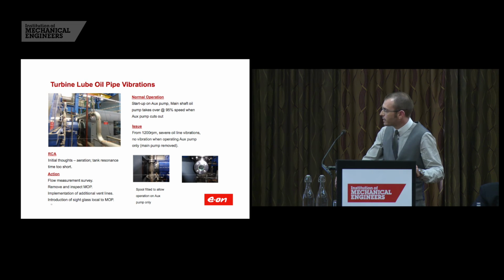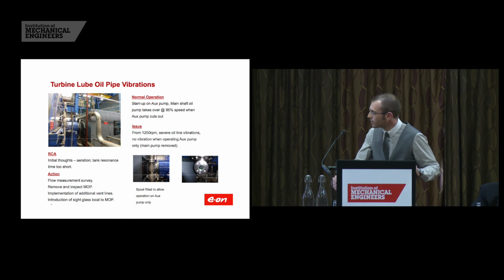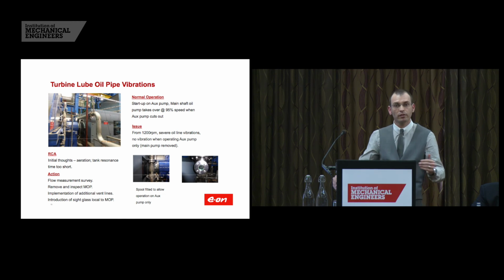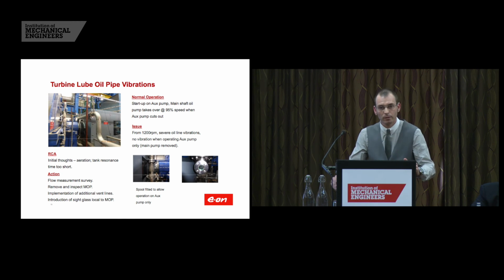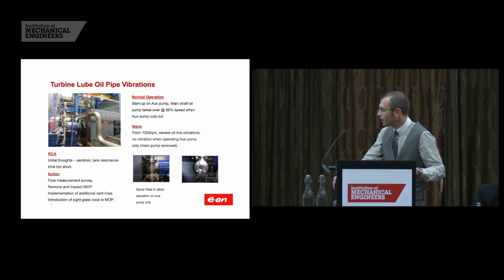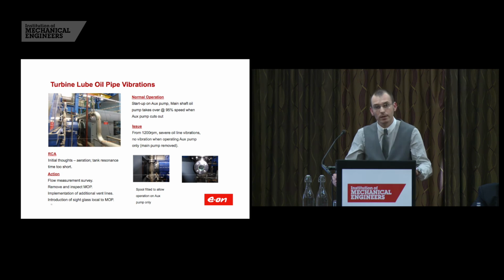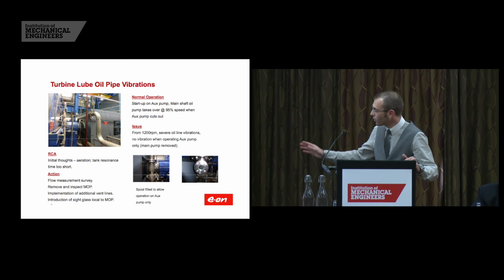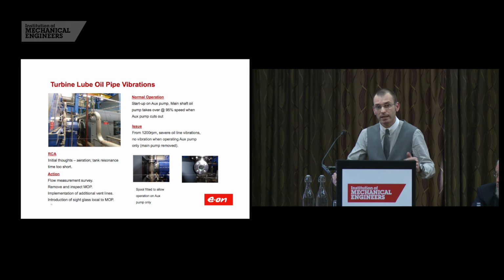So what actions did we take? When the machine was rebuilt and run, we decided to take a flow measurement survey to ensure that the flows of the system matched the design from the turbine manufacturer. Obviously, we removed the pumps and did an inspection, which revealed no damage. The OEM introduced additional vent lines to see if this was the root cause of the problem. And then on our guidance, we installed a sight glass so we can physically see what the oil was doing, which gives a good indication if there's any air within the oil.